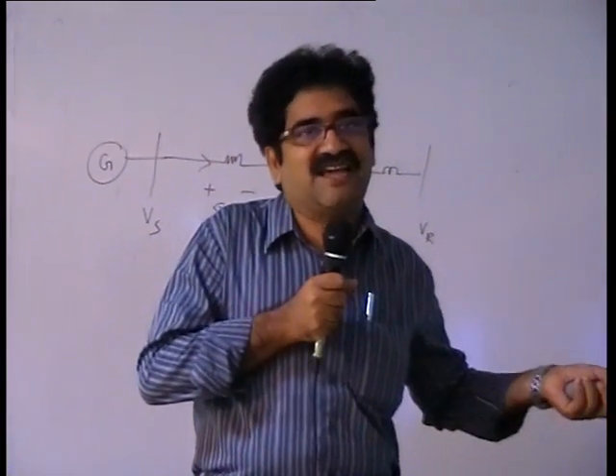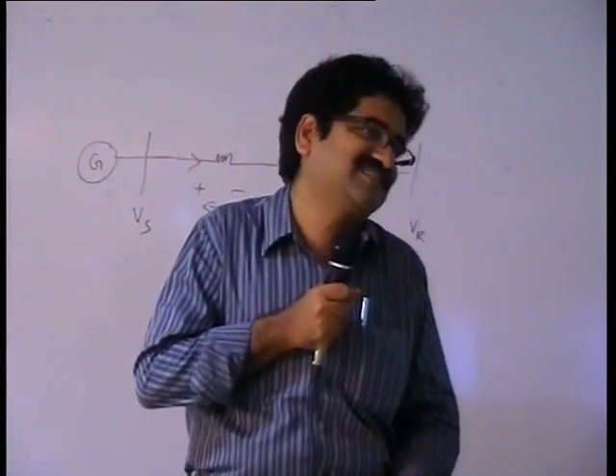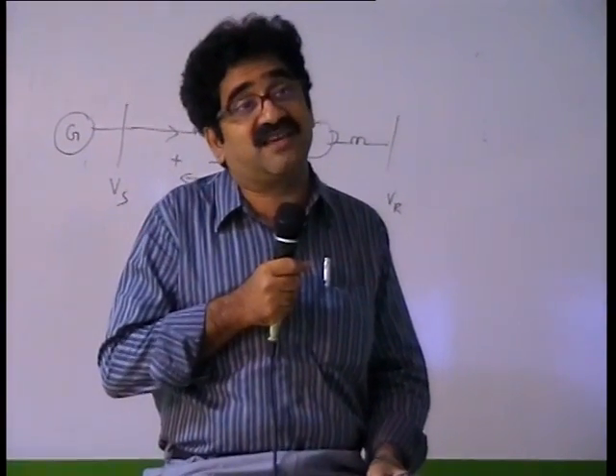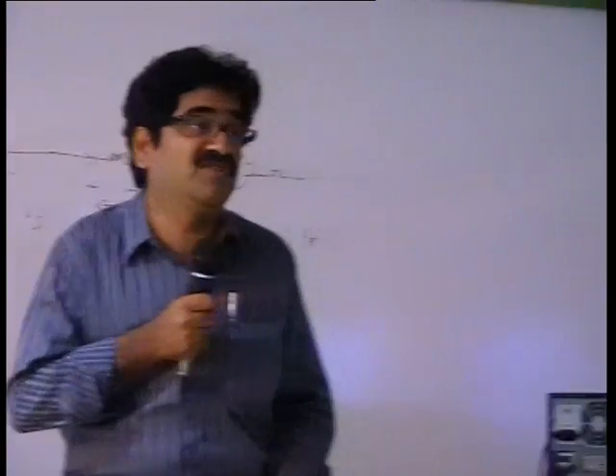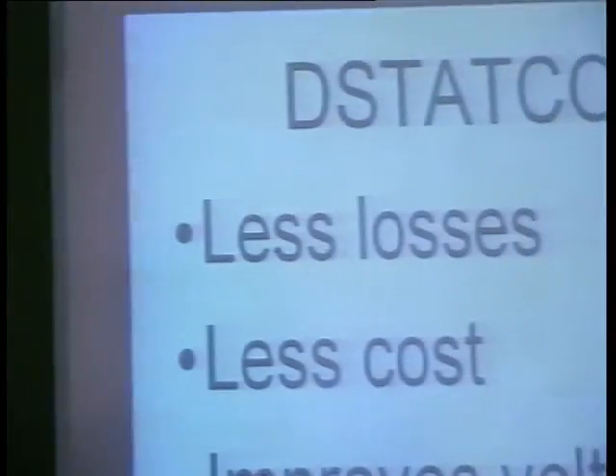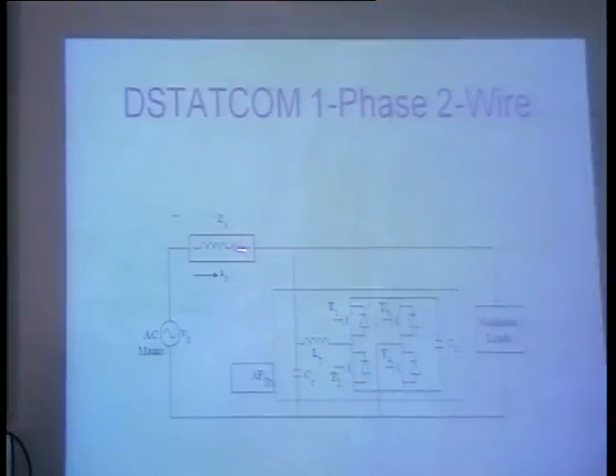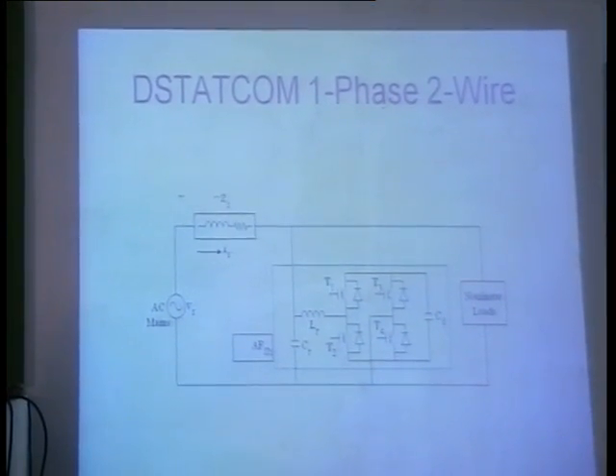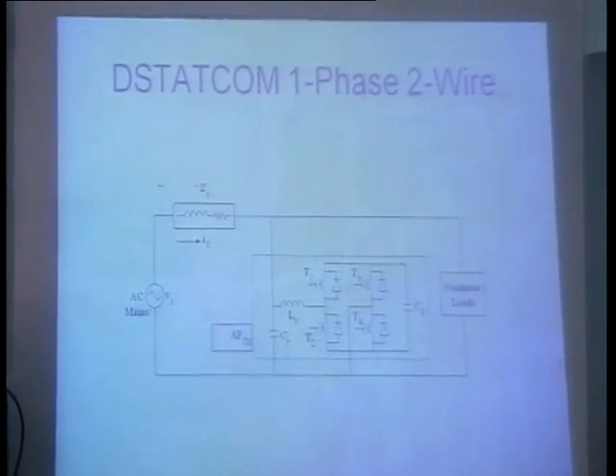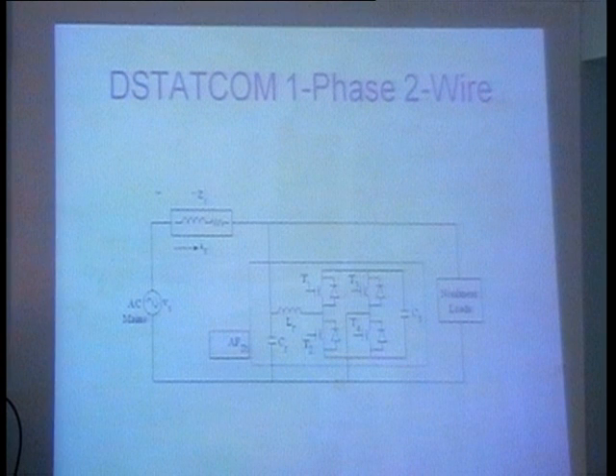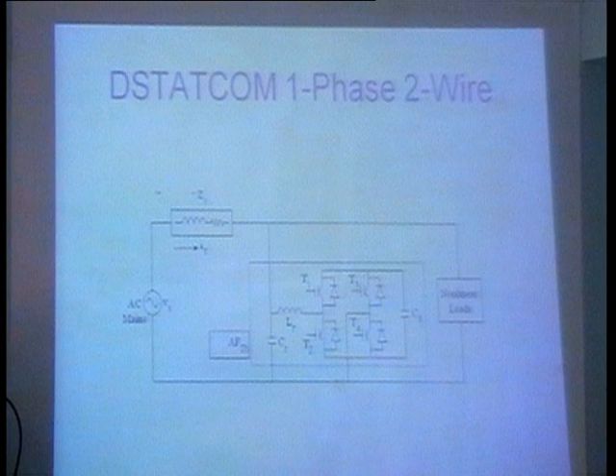STATCOM can operate at lagging power factor, leading power factor, or unity power factor. If you make the capacitor voltage in the STATCOM much less than the bus voltage, then reactive power will flow from the bus to the capacitor. Real power flows from high angle to low angle; reactive power flows from high potential to low potential. So if the bus potential is higher and the capacitor voltage is lesser, then it is absorbing reactive power.